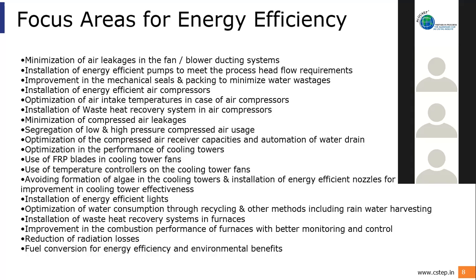We talk about the receivers of the air compressors. We are using air receivers with the compressor. Whether this receiver is allowing the necessary buffering to allow the compressor to load and unload properly, the capacity and sizing of the receiver, the sizing of the pipelines, and the sizing of the drain system for the air compressors is a very important aspect which will be catered to during the energy audit.